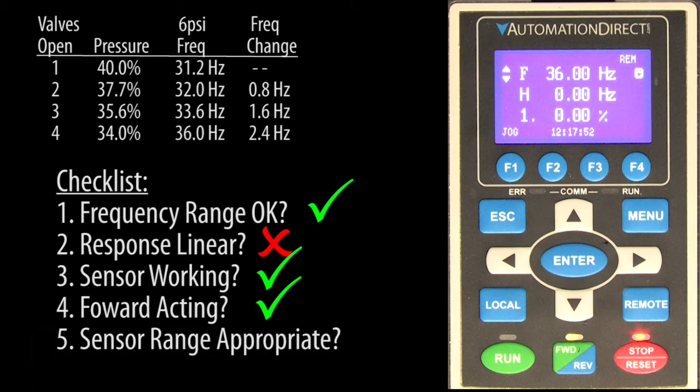We also know that the sensors are appropriately sized for the job. We are operating in the middle of the sensor's 15 PSI range. If we were using a 100 PSI sensor and we only needed around 6 PSI, then we would be using a very small portion of the sensor's range.